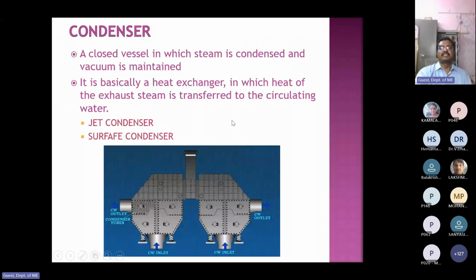Condenser is a closed vessel in which steam is condensed and vacuum is made. Vacuum is negative pressure. The output of the LP turbine is minus 0.9 or minus 0.91 kg per cm square with the help of the condenser. So in general, the condensers are of two types: jet condensers or surface condensers.